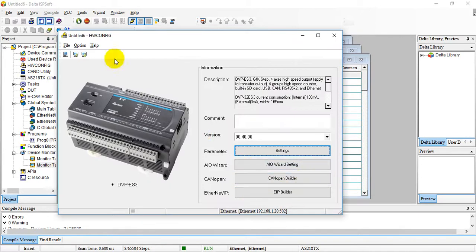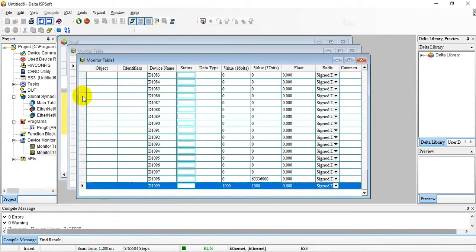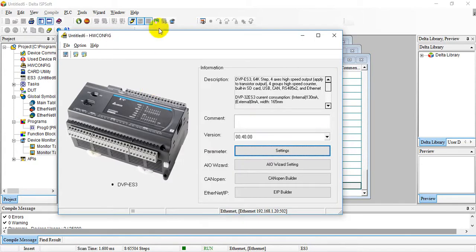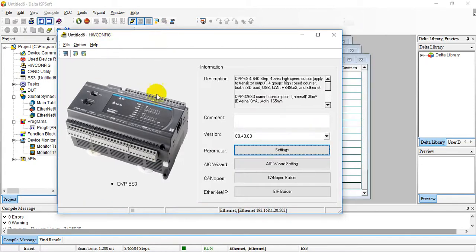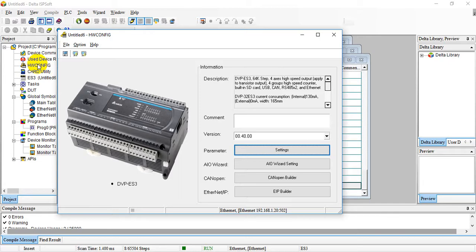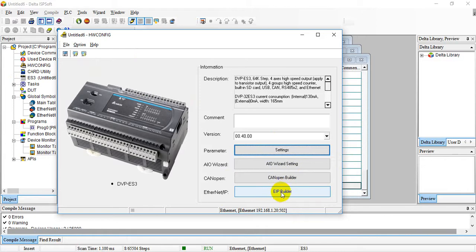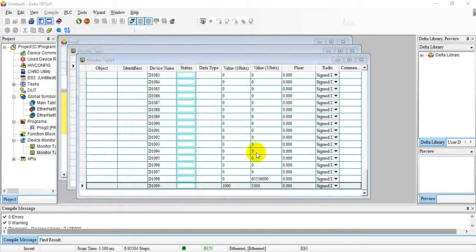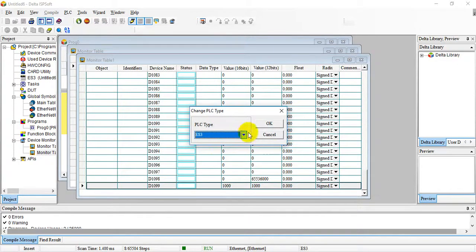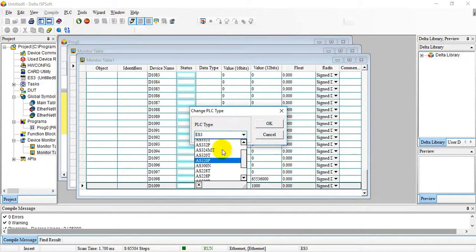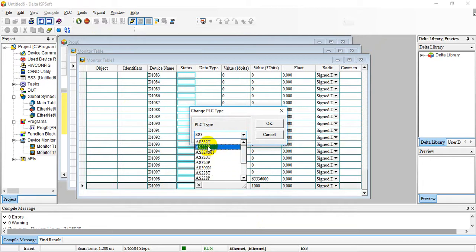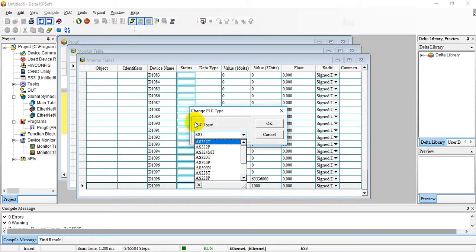One more thing I want to emphasize: let's switch here, you can find for ES3 PLC you can find hardware config over here, but for most of the DVP series PLCs, because this is an old design, you cannot find hardware config over here. Besides, you can do the AIO wizard and CAN OPEN or EtherNet/IP builder settings in hardware config, but this one is not available in ES2 or other DVP series. Remember, because ES3 shares the same CPU MCU with AS200 and AS300 series, this one we can migrate ES2 program to ES3. That's all, and thank you.